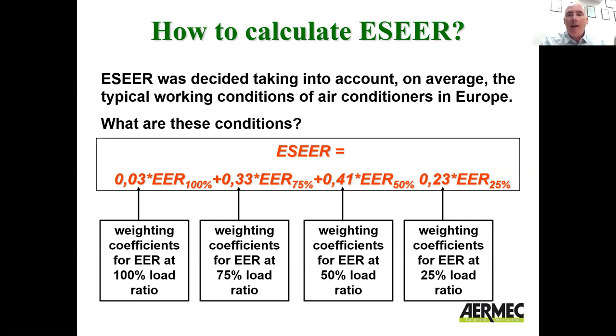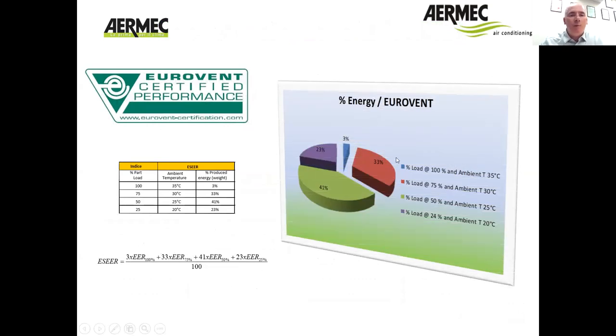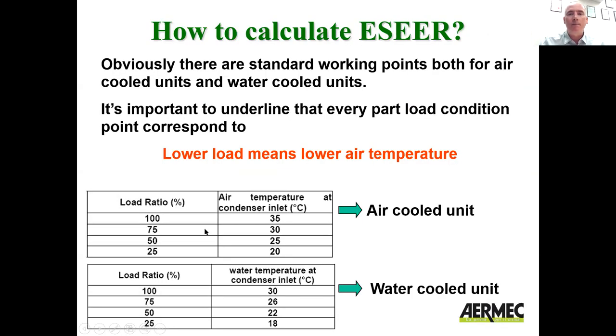By the way, AERMEC have all of their testing chambers — their climatic test chambers and acoustic test chambers — Eurovent certified. Just to show you here also: at 100% load, we assume the ambient is 35°C. At 75% load it's 30°C. As you can see, we assume that as the load drops, the ambient is dropping, for HVAC applications. If it's a water-cooled chiller, the temperatures being used are different, as you can see there.